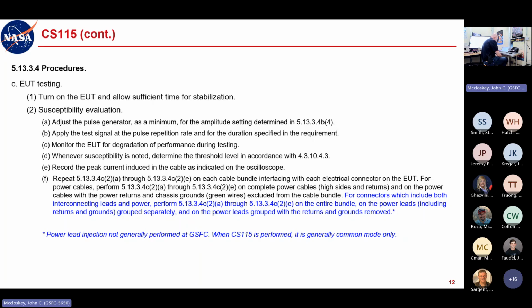and inject on it separately. So you can do that. We generally have not done that at GSFC. When we've used CS115, we've generally only done it as a common mode test. This is a judgment call that we have made. I mean, if you're dealing with some external stimulus, it's most likely going to be a common mode event that's stimulating an entire cable bundle and not really something that's going to be specific to a power lead, as opposed to only the power lead and not the return.